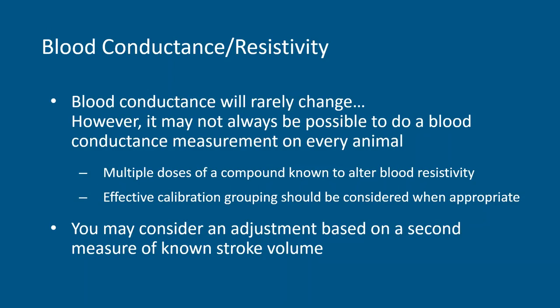Now, we have calibrated values potentially based on the cuvette, and we indicated that the resistivity stays relatively constant, although not always. The quickest way of checking is, if you are introducing some solution that you think may affect the resistivity, it's always a good idea to monitor the pressure volume loops and see if they're moving back and forth or getting bigger for no apparent reason. This could be a sign that whatever drug you're using may actually alter the conductivity of the blood and may need to be adjusted for.